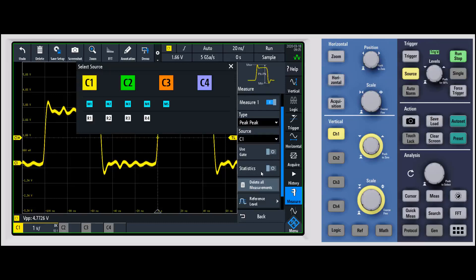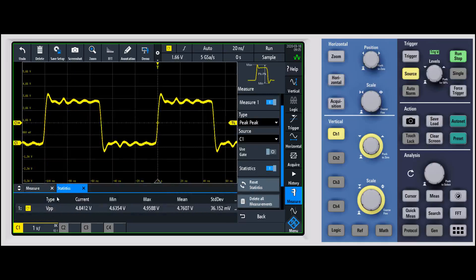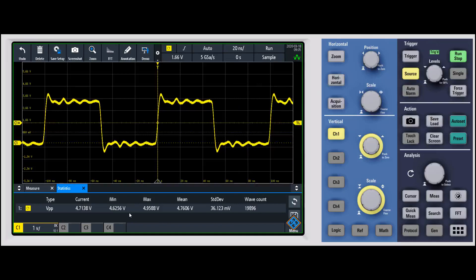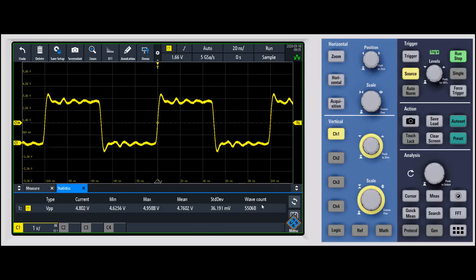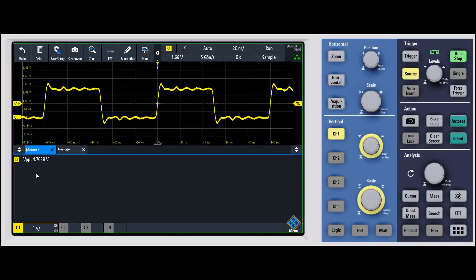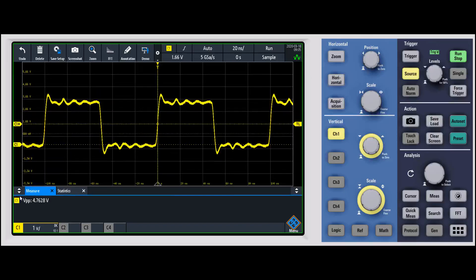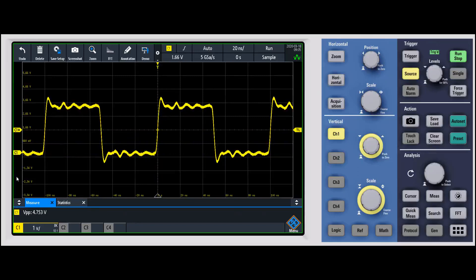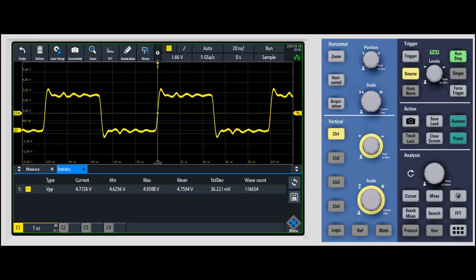The next thing I'll jump to is statistics, which is a really good one because it gives you an additional bar with statistical information on the measurement itself. For volts peak-to-peak, you can see the current value, the minimum, the max, the mean, the standard deviation, and how many waveforms the measurement has been made on. The RTM3000 does a quick job of accumulating waveforms for accurate measurements. You can also adjust the size of that table or jump back to just the measurement itself to save screen space — it will lay them out horizontally. You can also save off the statistical data.